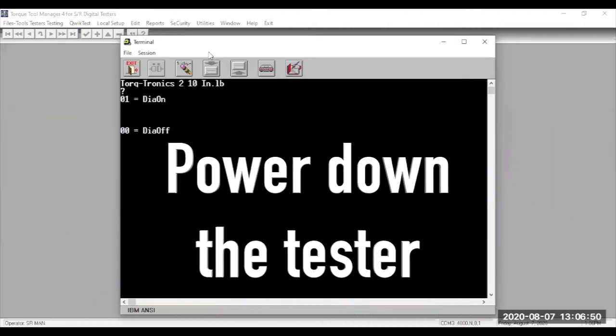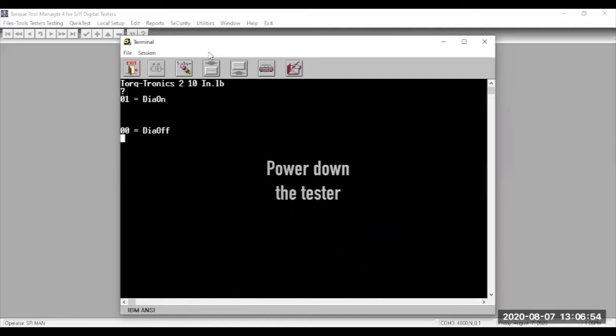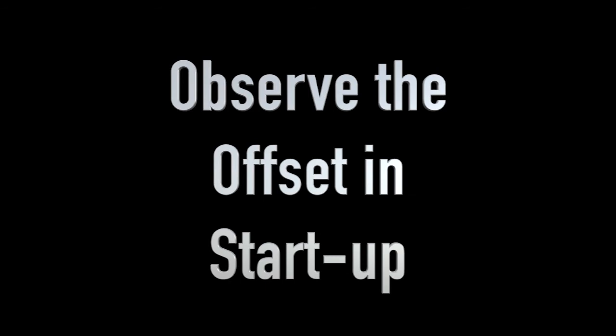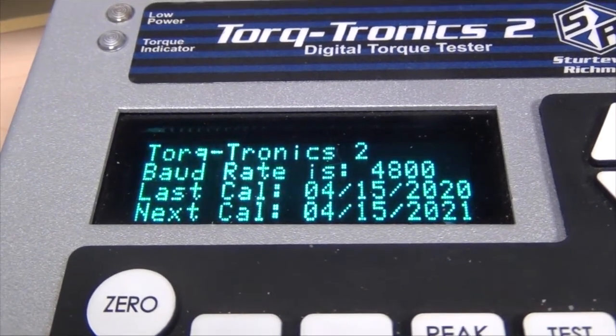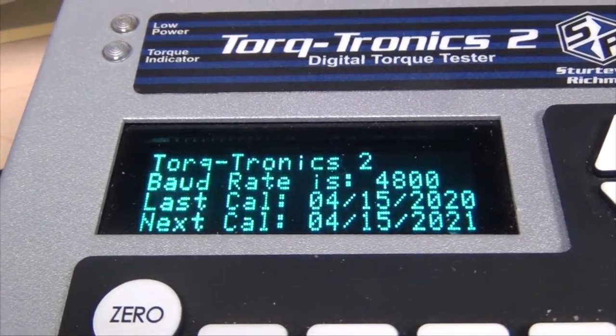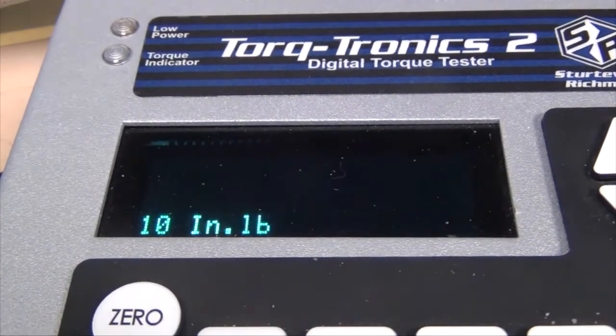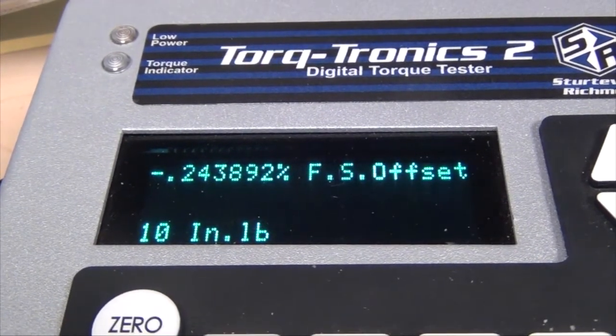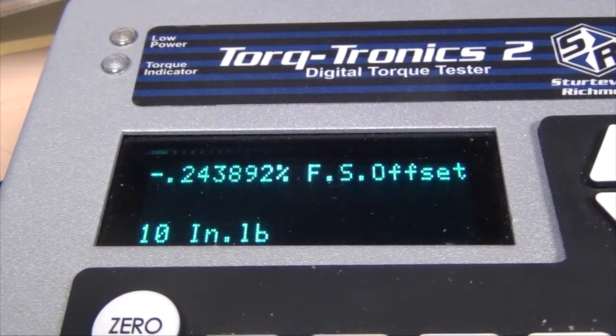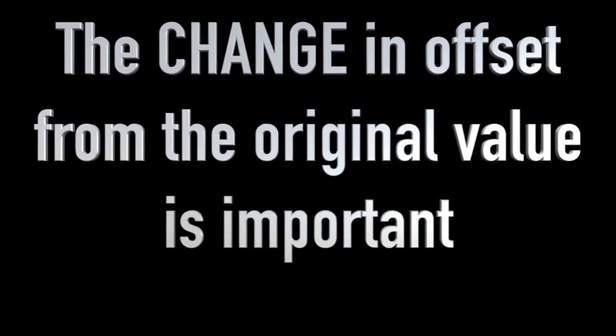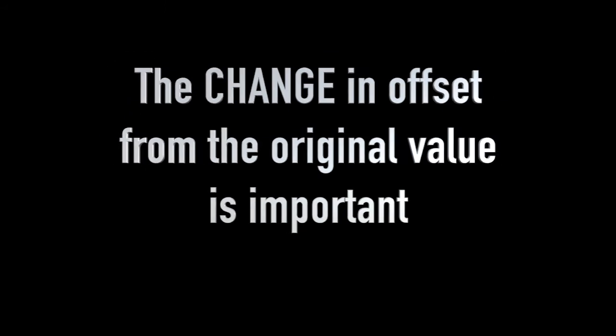Turn off the power, count to 7, and then flip the power switch on the tester back on so the tester has power. The third screen in the startup sequence shows you the offset. It appears briefly, so pay attention. We're looking at the size of the offset. We convert electrical energy into a torque equivalent value.